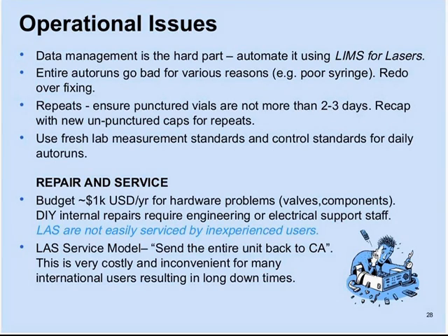Which leads me to one of my pet peeves, the laser service model that we are stuck with today. Generally, when you run into serious problems, the response from both companies is send the whole unit back to California. Now, this is costly and really inconvenient for many international users and results in long downtimes. So again, I would encourage the companies to try to make user serviceability something that can be looked at into the future. I know it's not possible in many cases. And I think it was Elena alluded to that about the cleaning.